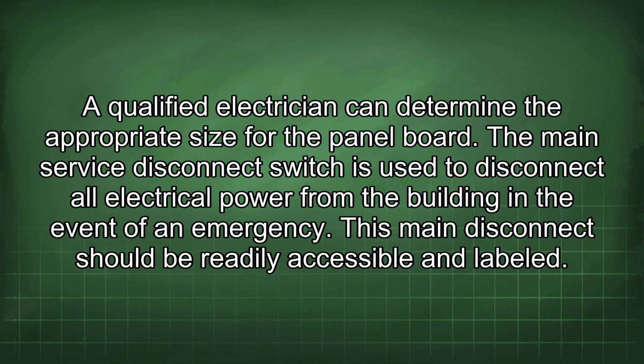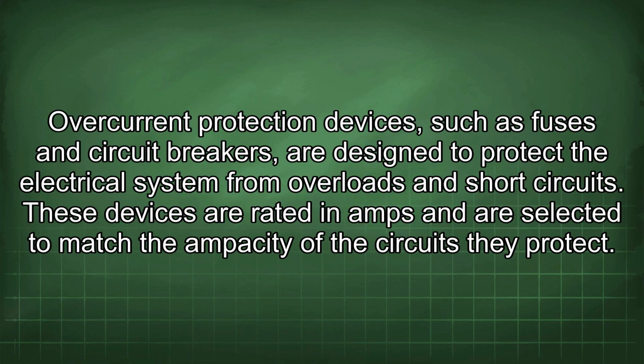The main service disconnect switch is used to disconnect all electrical power from the building in the event of an emergency. This main disconnect should be readily accessible and labeled. Overcurrent protection devices such as fuses and circuit breakers are designed to protect the electrical system from overloads and short circuits.